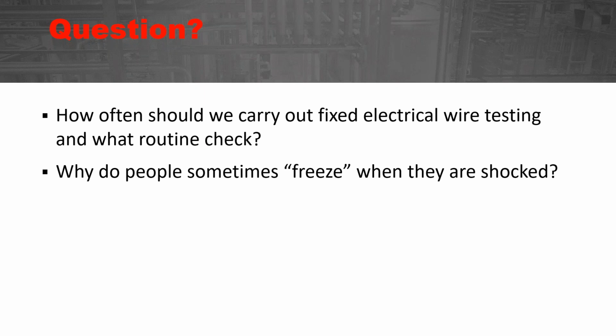So to answer the first question, first off, it's very vague and open-ended. I'm assuming when you mean electrical wire testing, you're looking at maybe insulation resistance testing or hipot, or even pressure connection testing, like making sure that there's a solid connection between one conductor and bus bar or between conductors. And I would say follow the manufacturer's recommendations on when and where and how to test. Frequently, I commonly see anywhere between 1 year and 5 years when it comes to performing standard maintenance on electrical equipment. And it's all based on what the manufacturer recommends, and it's all based on your environment and your operations and basically how you utilize the equipment.